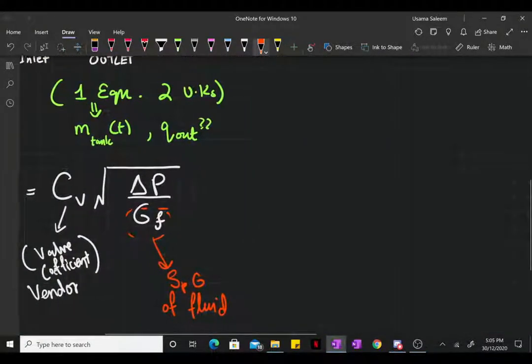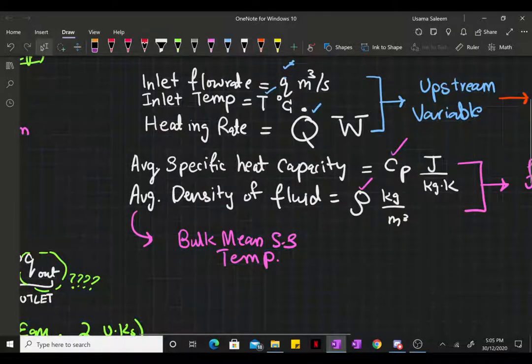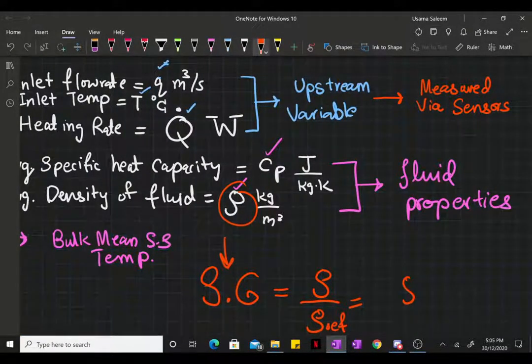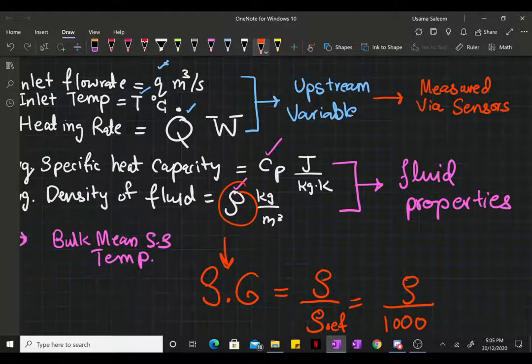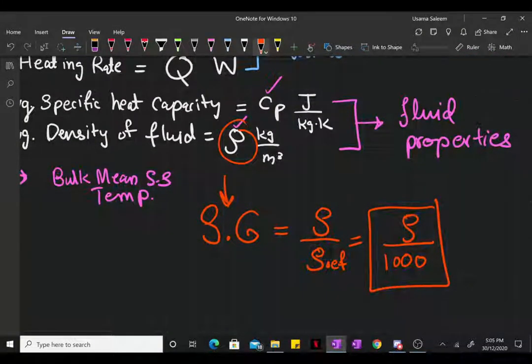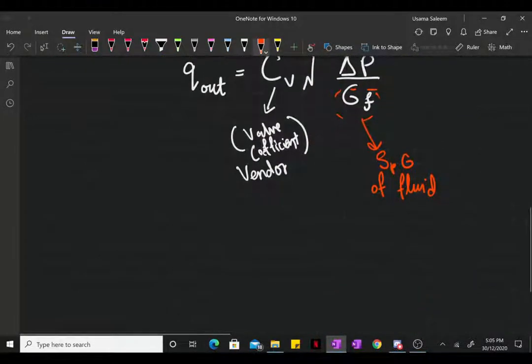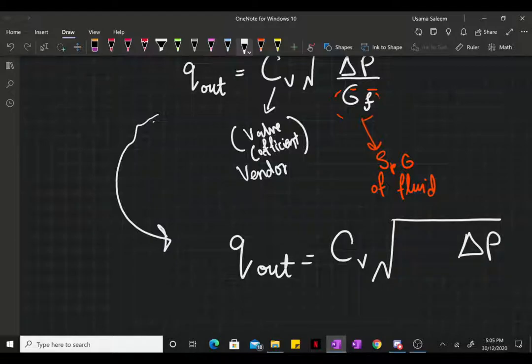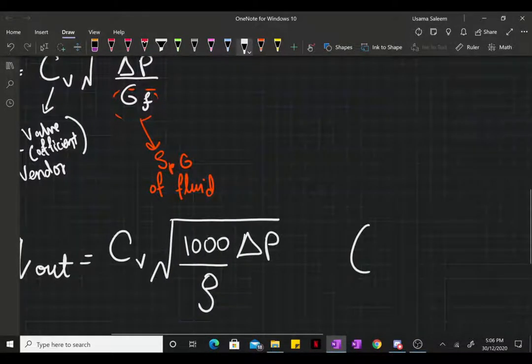We know the density of the fluid, right? So the specific gravity is just going to be density divided by the density of the reference fluid, which in this case is going to be water for most commercial valves. Given that, this valve equation turns out to be Q_out equals CV square root of (ΔP × 1000/ρ). Everything is in SI units.